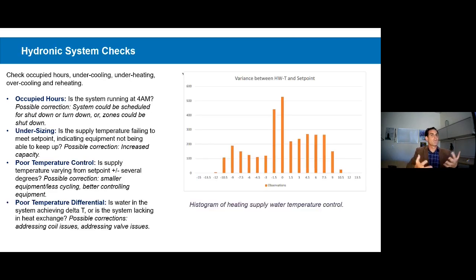Here are some of the checks that we would be looking at on a hydronic system. The list is very, very similar, right? And again, we frequently see poor temperature control in hydronic systems. The graphic on this page is a pretty typical example, plus 10 degrees, minus 12 degrees.